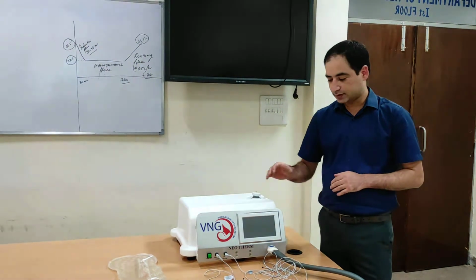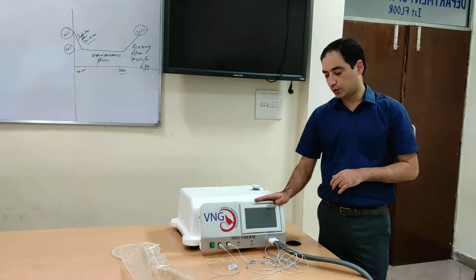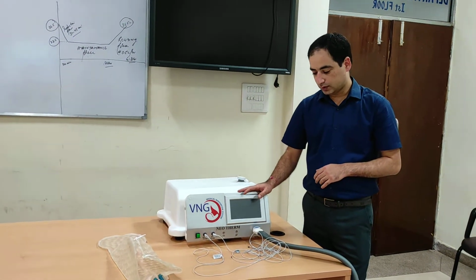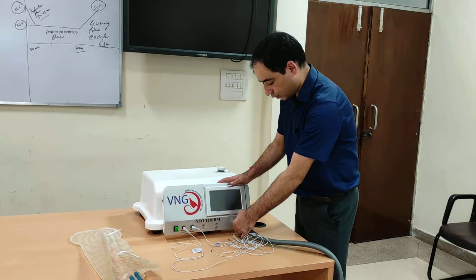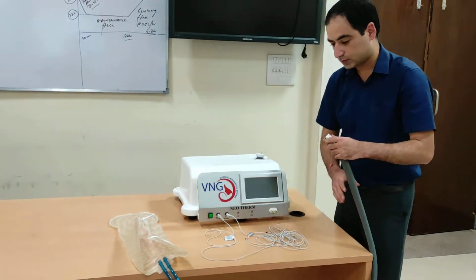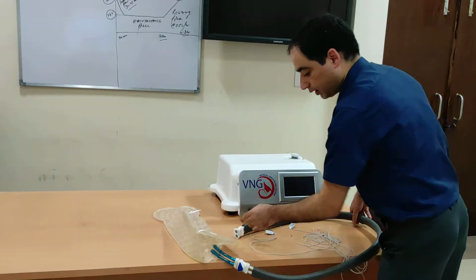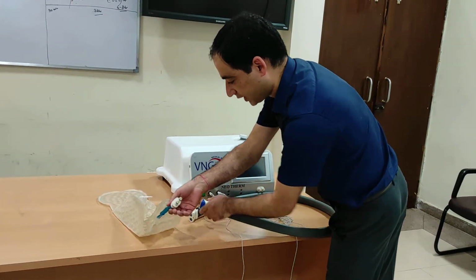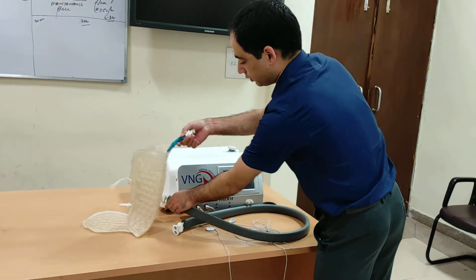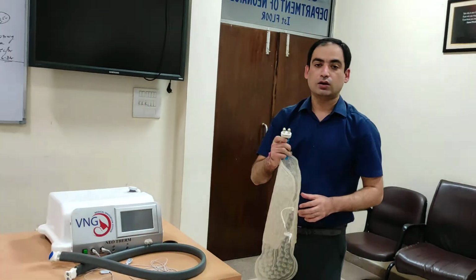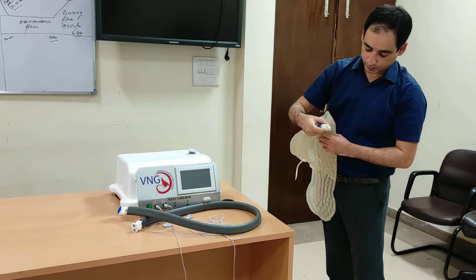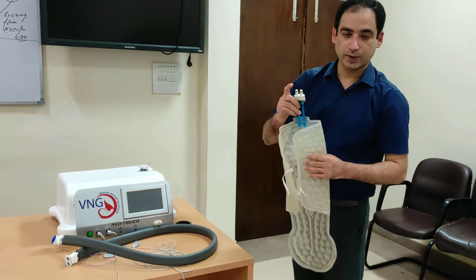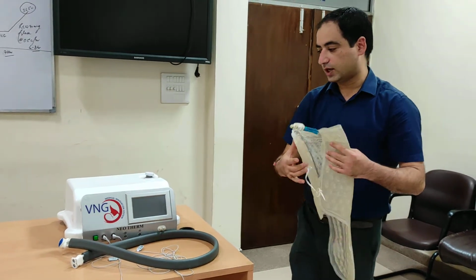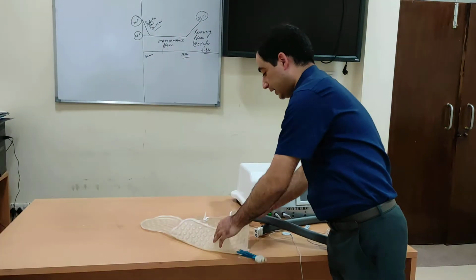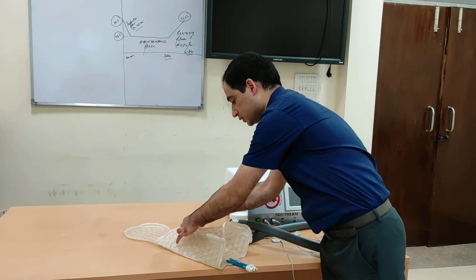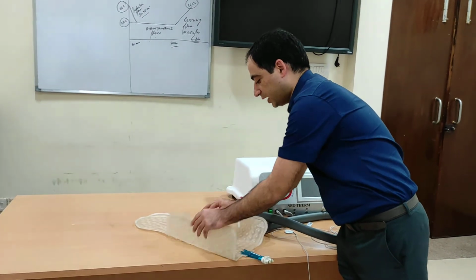And once we have completed the therapy, that is 72 hours of cooling, 6 to 8 hours of rewarming, then we should switch off the machine, press on this blue button and take out this hose pipe both from the machine as well as from the baby jacket, and then this water should be removed after each use. You can press it here and you can see that the water is coming out. Once we have taken this water out from the jacket, it should be cleaned with an antiseptic solution after each use and should be stored in a proper place as per manufacturer's guidance.